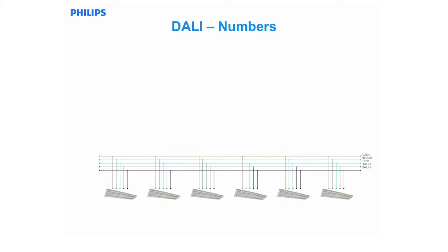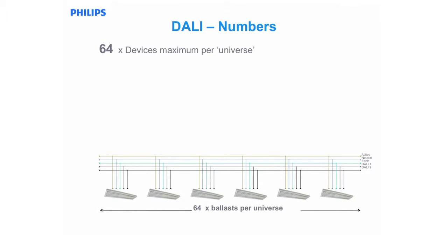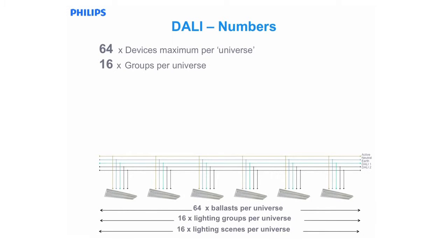As DALI is a communication protocol, there are some addressing limitations within the system. These limitations are common within all DALI systems and should never be exceeded. A DALI universe cannot have more than 64 DALI addressable devices. The 64 light fittings on a single DALI universe can be divided up into 16 logical groups. This allows for the lighting to be coordinated together. Within each of the 16 lighting groups, 16 lighting scenes can be recalled.